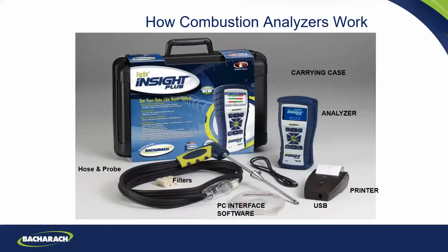You're going to watch that temperature come up in the stack of the appliance, the furnace, or boiler you're working on. You're not going to really read your efficiency until it comes up to what's called steady state efficiency, and you're going to do that by looking at your temperature. So in a high efficiency furnace, maybe it's going to come up 60, 70, 80, 90, 100, 110, and then 120, 123, 122, 123. You're just hovering there. If it starts hovering somewhere, that's where you're going to take your test.